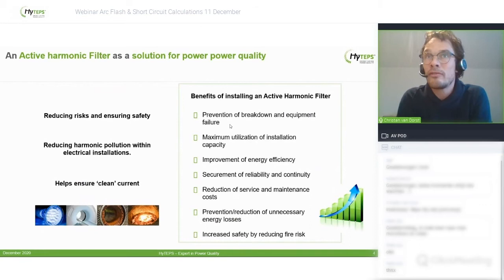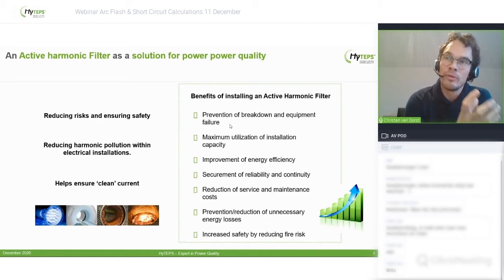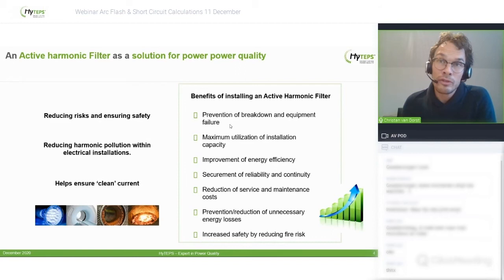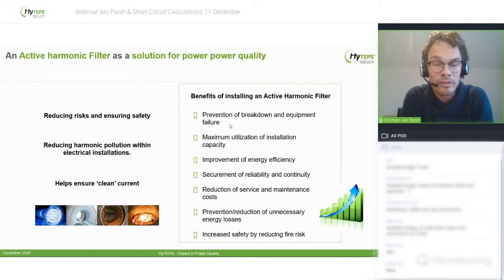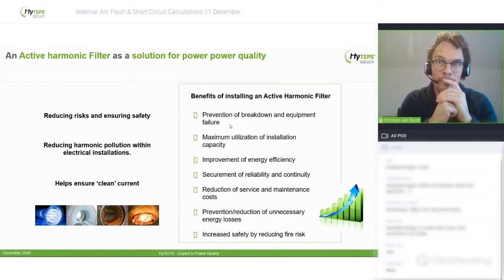An active harmonic filter is a system that continuously measures the quality of the current and compensates the harmonic distortion present, and by compensating the harmonic current it also improves the voltage. Active harmonic filters are a very efficient and flexible tool when you experience harmonic distortion problems. Apart from harmonic distortion, the active filter can also address unbalanced issues — for example, if L1 is loaded with a very high value and L2 and L3 are less loaded, the active filter can balance these currents so the generator can be used more efficiently.